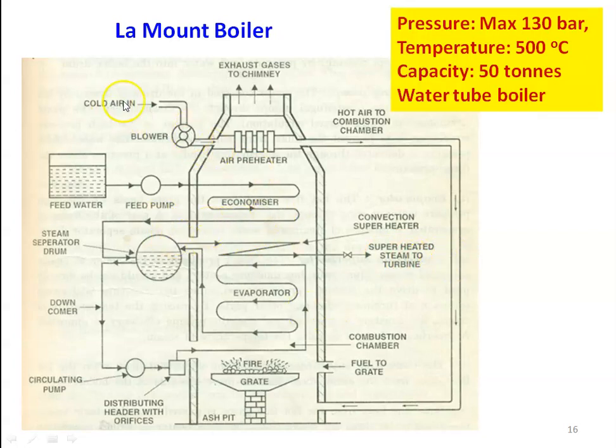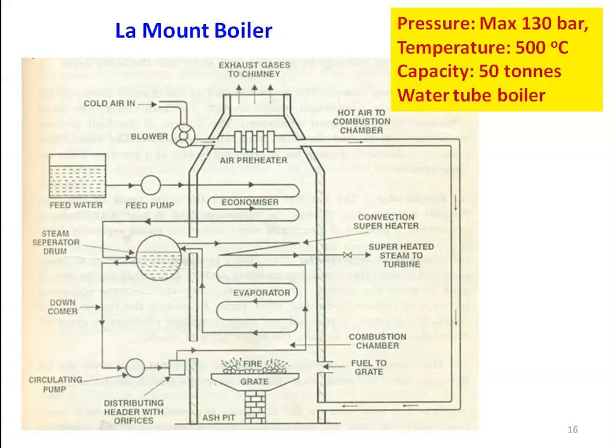Atmospheric air enters using a blower and is circulated to the air preheater. In the air preheater, the air absorbs the heat energy of the waste gases. The air temperature is raised, and when hot air is supplied to the combustion chamber, combustion efficiency is better, giving complete combustion of fuel and more heat with less fuel. The air preheater is also an accessory installed to improve the efficiency of the boiler plant. So here we have three accessories: superheater, economizer, and air preheater. The feed pump is also an accessory used to provide forced circulation of water, which improves the efficiency of the boiler.